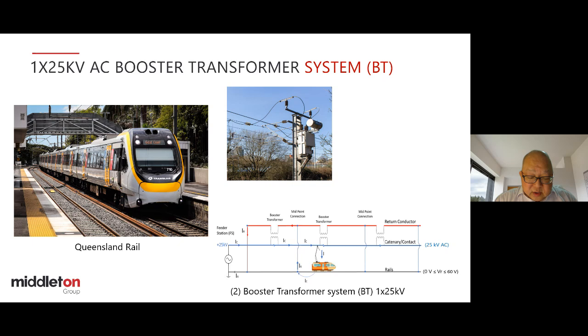Now, what are the cons? The BT system is obviously more expensive than the rail return system, as it requires additional equipment: booster transformers, midpoint connector, return conductor, and bypass switches for the air gaps as well, in case you want to bypass a booster transformer. And of course, there are more components for maintenance people. Next slide.